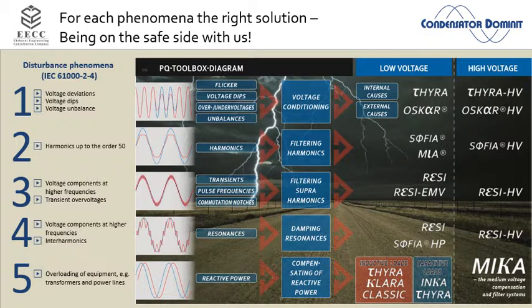Now, if you buy a Danfoss inverter or an SMA solar panel inverter and you open it with a screwdriver or your penknife, it doesn't make you very popular with the customer, you can't close it afterwards again. And you find 6 of these like that on the grid side. What could that be? That size, white. What thing could be written on there? Very typical 50 microfarad capacitor for EMC problems on the input side of a drive. Now let's say behind my 1 MVA transformer I have 6 of these drives. Okay, then I have 6 times 50 microfarad. Makes it 300 microfarad.